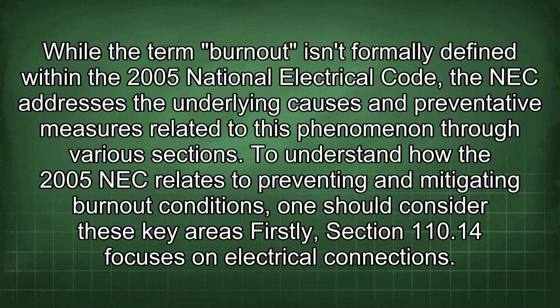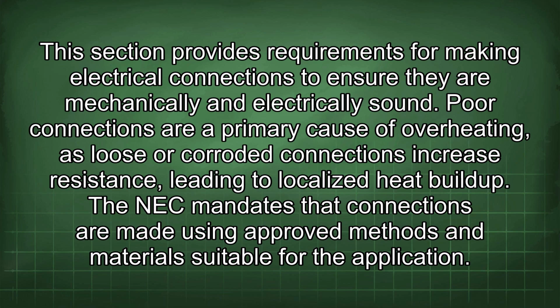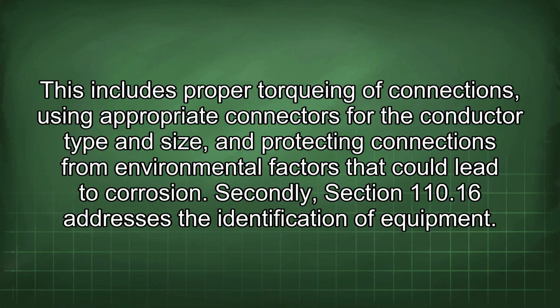Firstly, Section 110.14 focuses on electrical connections. This section provides requirements for making electrical connections to ensure they are mechanically and electrically sound. Poor connections are a primary cause of overheating, as loose or corroded connections increase resistance, leading to localized heat buildup. The NEC mandates that connections are made using approved methods and materials suitable for the application. This includes proper torquing of connections, using appropriate connectors for the conductor type and size, and protecting connections from environmental factors that could lead to corrosion.